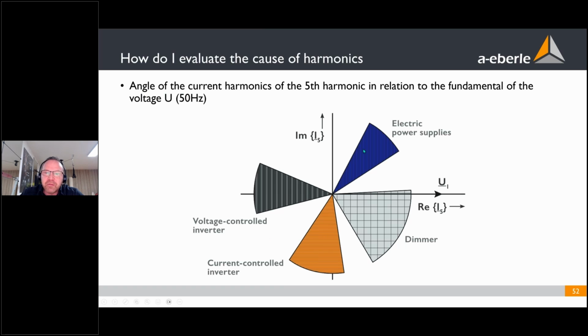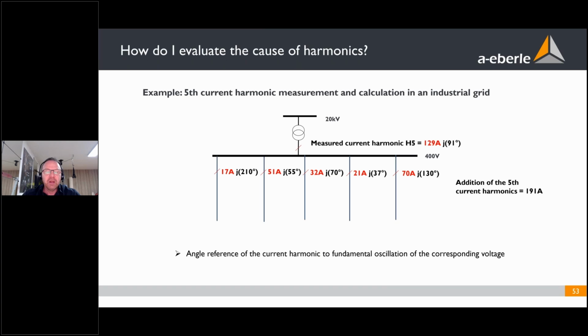It's good that we have a lot of different devices, and all the different devices can produce the 5th harmonic, for example, in any angle. So electronic switching power supplies, single phase, often produce the disturbance of the 5th in this range. Industry, big 3-phase frequency converters, produce the 5th harmonic in this area. So both together for the grid is positive if you have this constellation. So the best way is you compare not the phase angle from voltage 5th to current 5th harmonic, but you compare the phase angle compared to the fundamental.